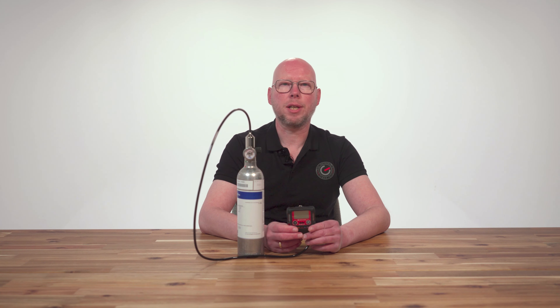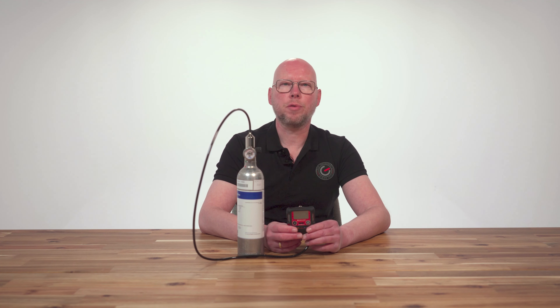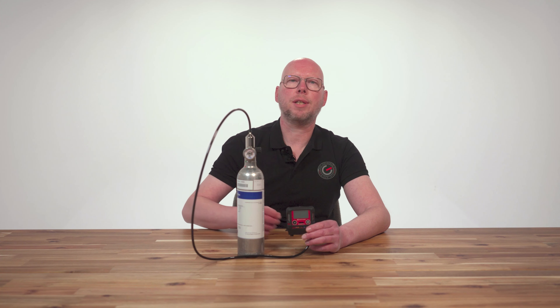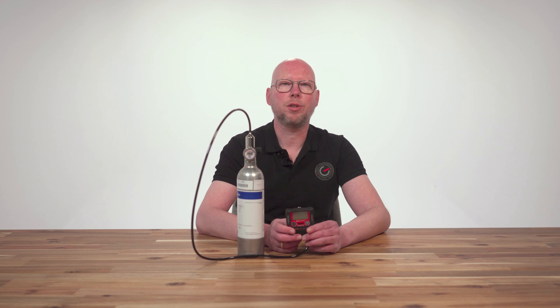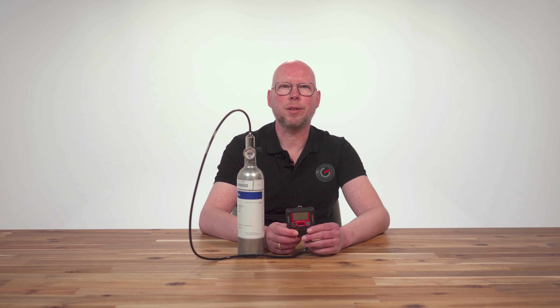Before you perform the gas check, make sure that you have first done the starting up procedure and the fresh air calibration. The calibration gas that we use for the GX3R Pro is the 58-liter RIKEN gas mixture, which contains 15 ppm CO, 25 ppm H2S, 2.5% CH4, and 18% O2.